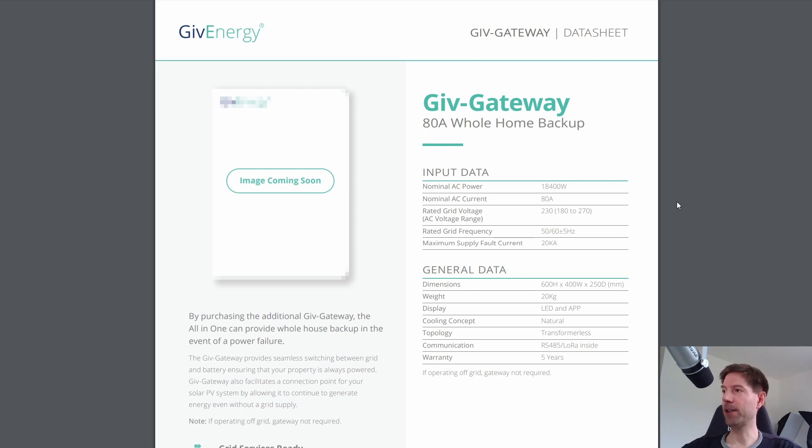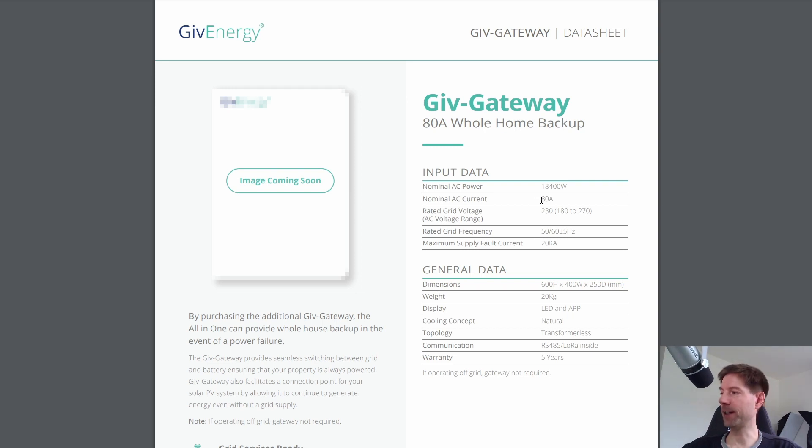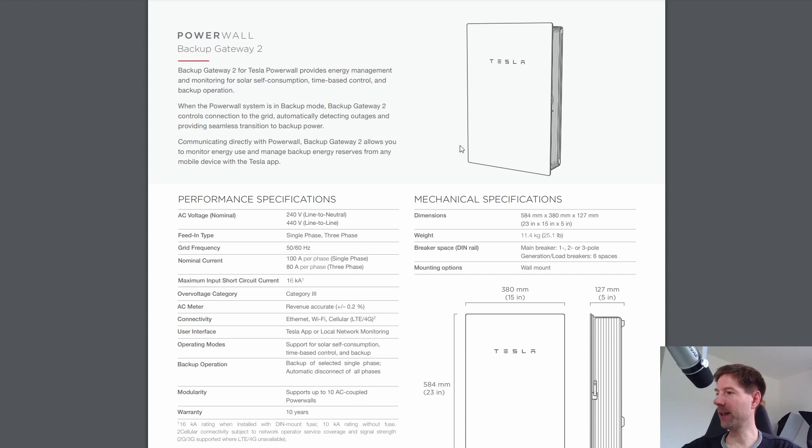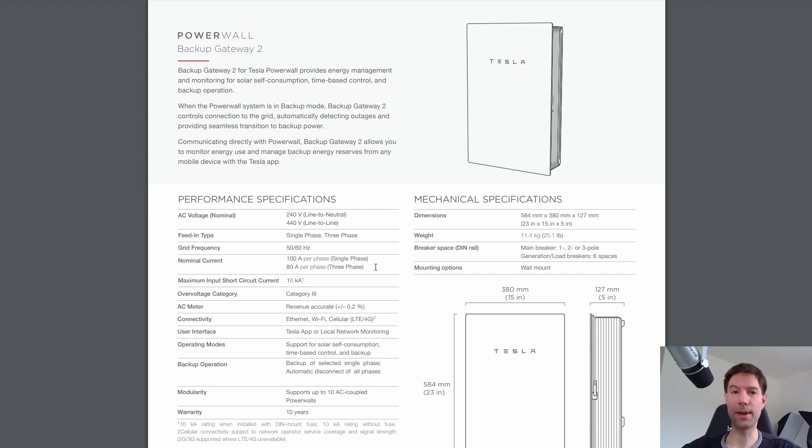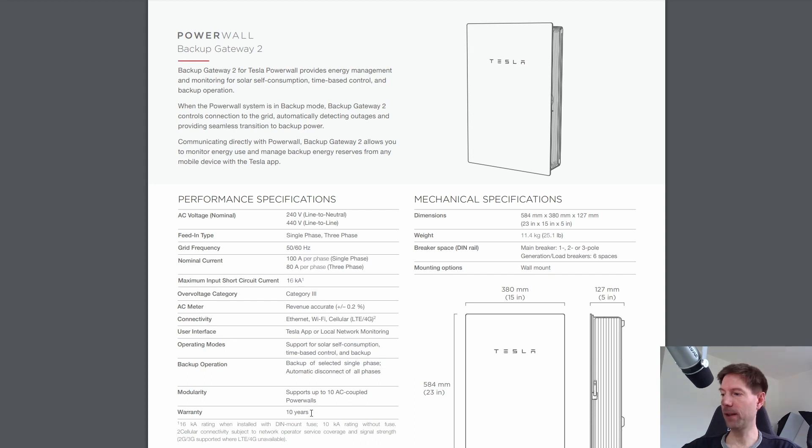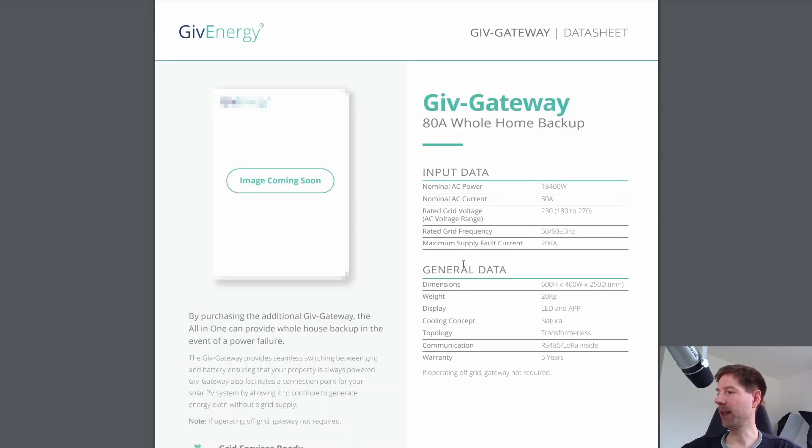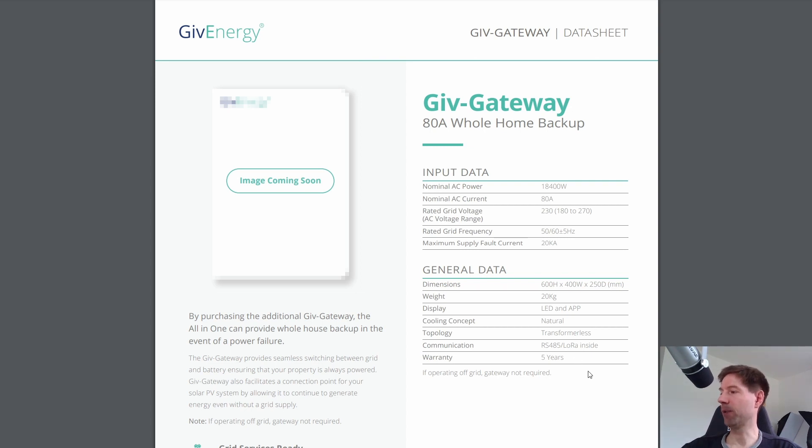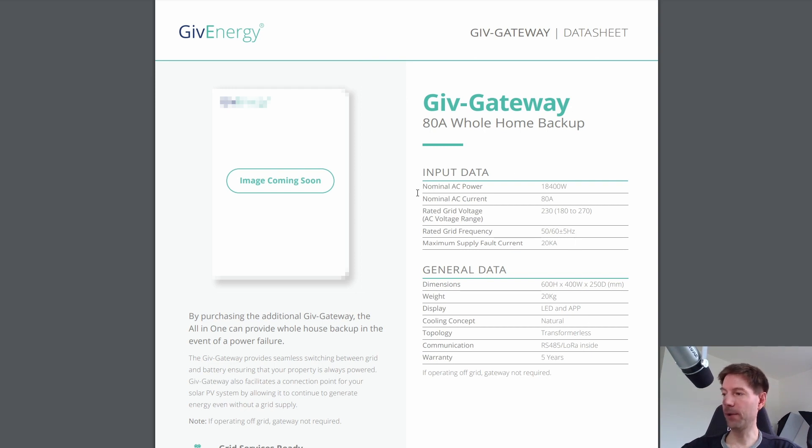And this works in a very similar way to the Tesla backup gateway that they have for their Powerwall. So this is rated at 80 amps. The Tesla gateway is rated at 100 amps if it's on single phase, 80 amps for each of the three phases if you're on three phase. But otherwise these are pretty similar. Again the warranty for the backup gateway from Tesla is 10 years whereas the warranty for the GiveEnergy gateway is five years much as with the all-in-one battery.